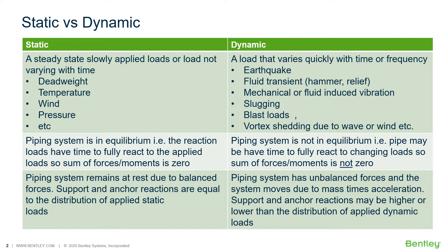In simple terms, a static load can be considered as a dynamic load with a long duration, so the piping system can fully respond to it. Dynamic loading will tend to increase the response of the structure beyond the response obtained if the same load is applied statically. The response of the system depends not only on the magnitude of the applied force, but also the frequency, or the timing of the load.